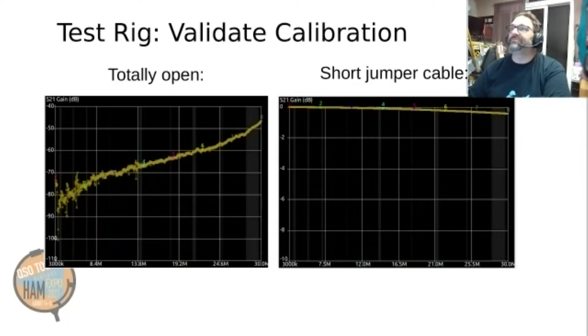And then you want to test with a jumper cable between those two ports, just a cable going from one to the other. And that should be very little loss, right? Again, down here at 3 megahertz, we've got basically 0 dB of loss. And up at 30 megahertz, we've got not even a dB, right? Because this is from a 0 to 10 range, so less than a dB worth of loss on the high end. So this is pretty good. This could be better, but here we are. Point being, validate your calibration, because I've seen some where my calibration was off and these graphs were way worse.